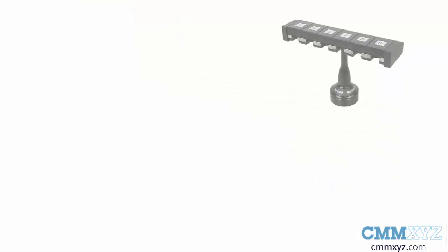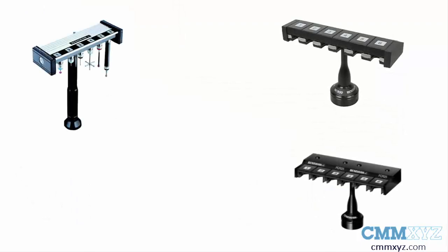In this video, the steps taken to prepare for calibration can be used for any probe changer that PC-DMIS supports. Before we start, calibrate the required probe modules and clamp the probe changer on the CMM at a suitable position.